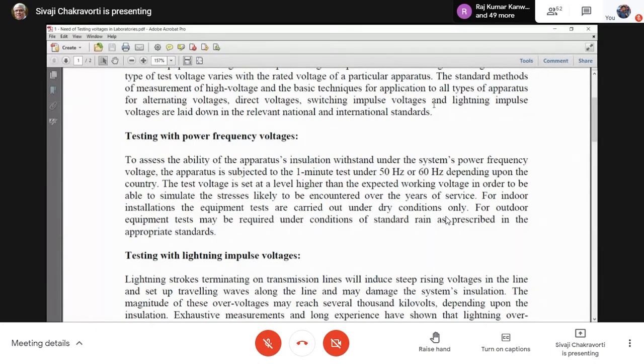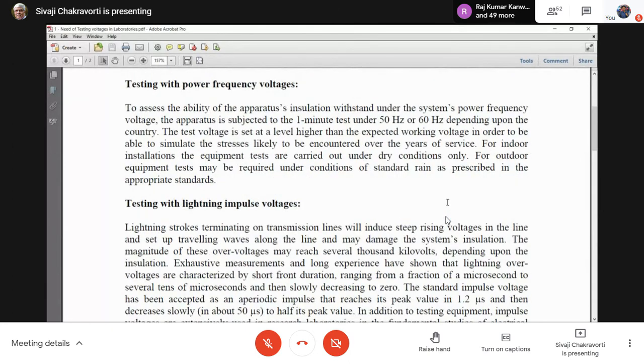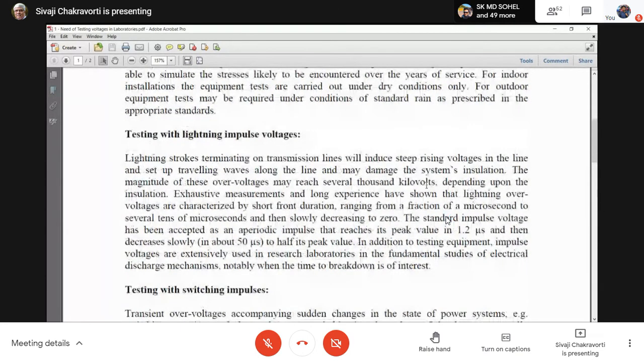Similarly, there will be over voltages due to lightning, because lightning is beyond the control of anybody. And these lightnings are very high voltage. But again, there are standards for that. And lightning over voltages have a typical wave shape. It is not power frequency, it is not AC, it is an aperiodic wave. So we have to generate that voltage as per the required shape and required magnitude. So we need specific testing equipment for generating those voltages. I will try to explain to you how we do that.